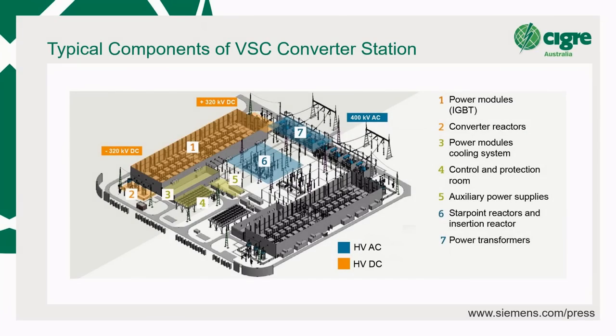So, typical components of a VSC. This is a diagram from the Siemens website. This is a symmetric monopole. You've got a converter, and this is actually two symmetric monopoles, so there's one here and there's one there. And this is the room with stacks of IGBTs connected to capacitors. That's really what's in this room, row upon row. Six rows, actually, to be precise. The phase reactors that I was mentioning before are sitting out here. There's a control room, because these converters require a fair amount of control and protection.